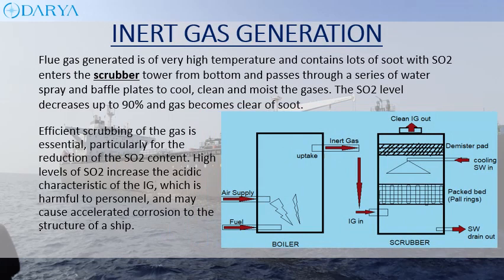Flue gas generated is of very high temperature and contains lots of soot with sulfur dioxide. It enters the scrubber tower from the bottom and passes through a series of water sprays and baffle plates to cool, clean, and moisten the gases. The sulfur dioxide level decreases by up to 90% and the gas becomes clear of soot. Efficient scrubbing is essential, particularly for the reduction of sulfur dioxide content, as high levels increase the acidic characteristic of the IG, which is harmful to personnel and may cause accelerated corrosion to ship structure.